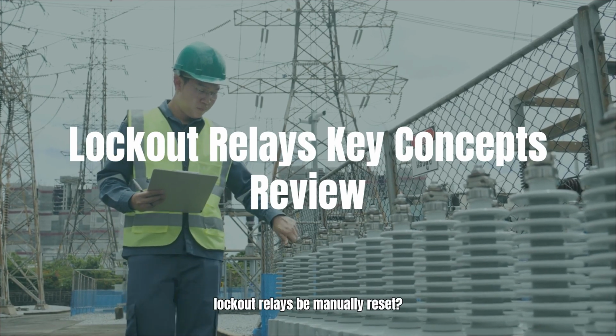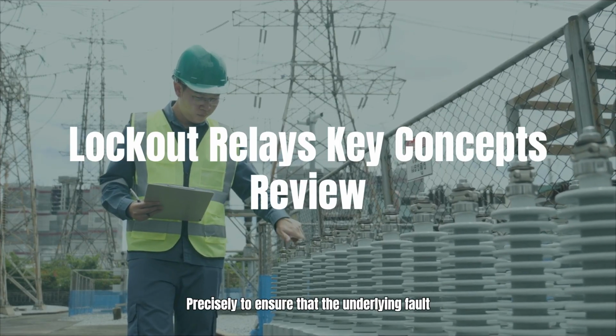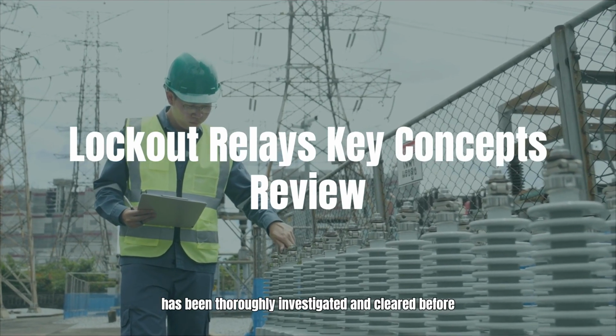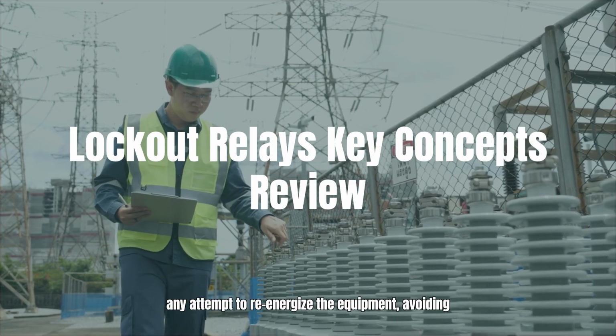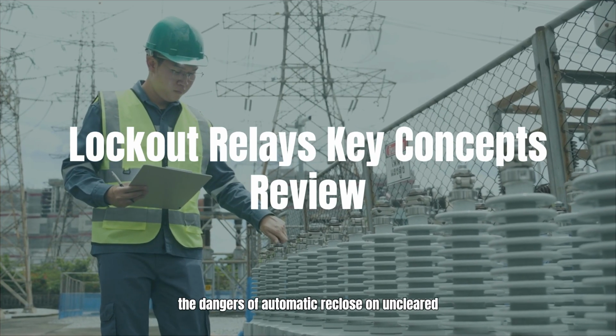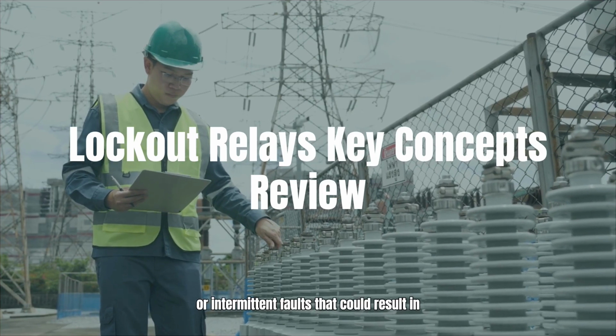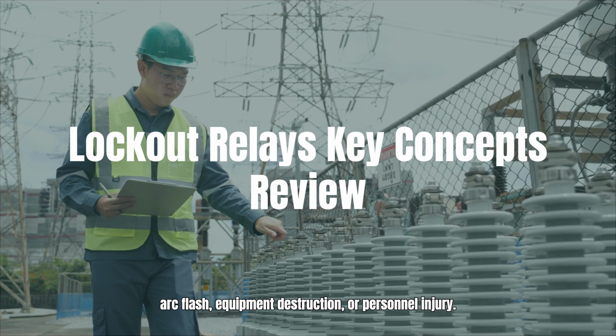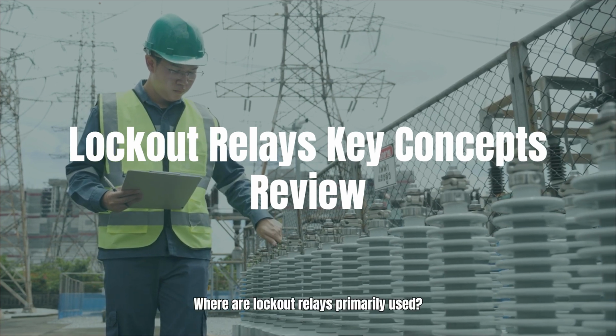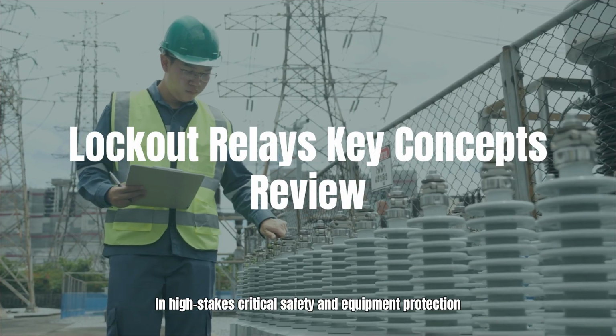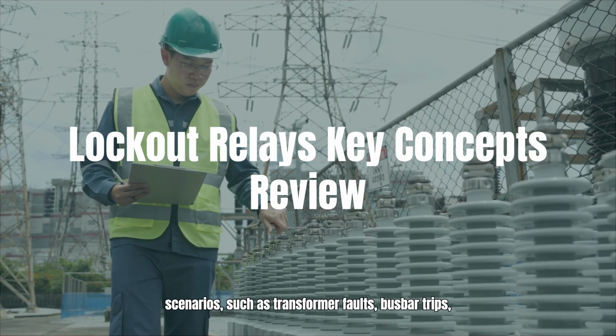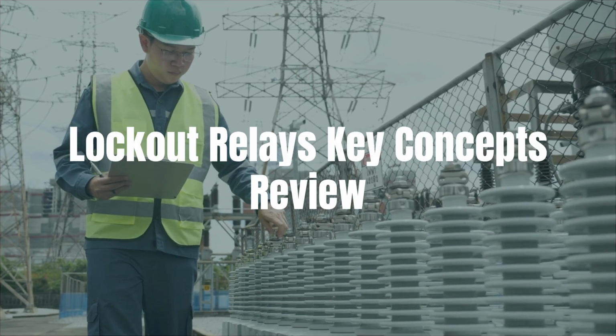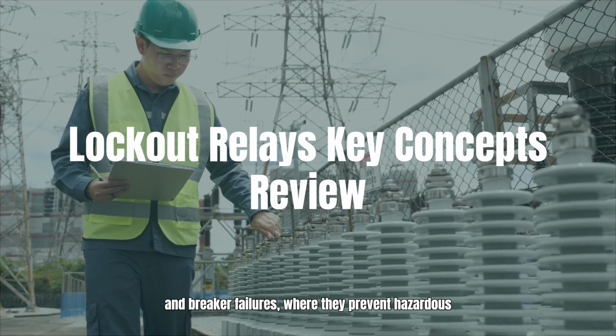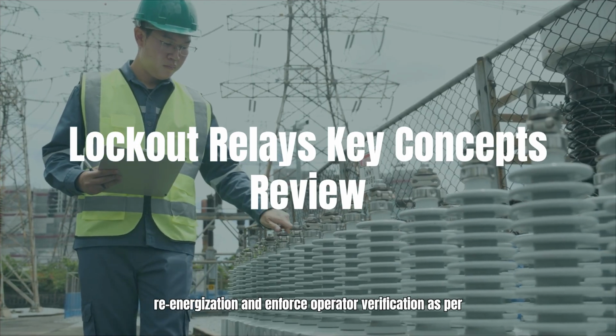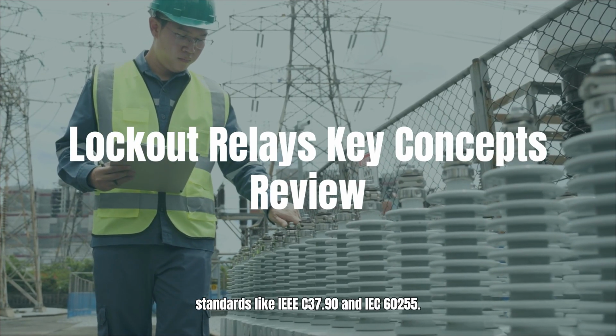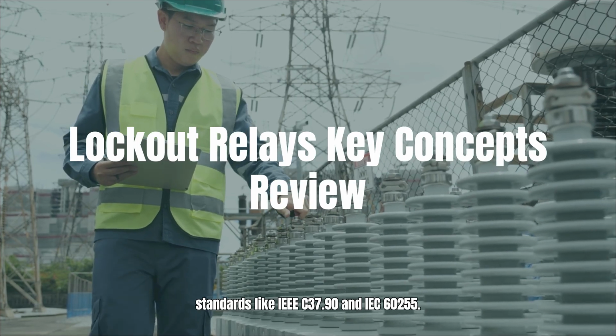Why must lockout relays be manually reset? Precisely to ensure that the underlying fault has been thoroughly investigated and cleared before any attempt to re-energize the equipment, avoiding the dangers of automatic reclosure on uncleared or intermittent faults that could result in arc flash, equipment destruction, or personnel injury. Where are lockout relays primarily used? In high-stakes critical safety and equipment protection scenarios, such as transformer faults, busbar trips, and breaker failures, where they prevent hazardous re-energization and enforce operator verification as per standards like IEEE C37.90 and IEC 60255.